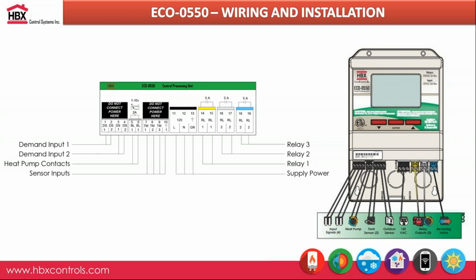In terms of wiring with the Eco 550, it's very straightforward. Demand input number 1 is for heating. 3 and 4 is for cooling. This could be a thermostat, 24 volts, or you can just put a jumper wire between them and always activate a heating or cooling call all the time. 5 and 6 is where you would always hook up the first stage of your heat pump. 7 through 10 is where you would put your sensors.